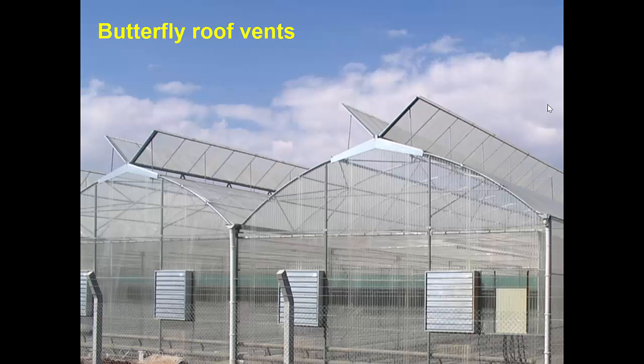Under highly dynamic outside climatic conditions, the best approach is to use butterfly vents where each side of the roof vent can be automatically opened, closed, or controlled depending on wind direction. Butterfly vents add flexibility to control of the natural ventilation process and can create an improved pressure gradient on the roof vent, contributing to improved ventilation.